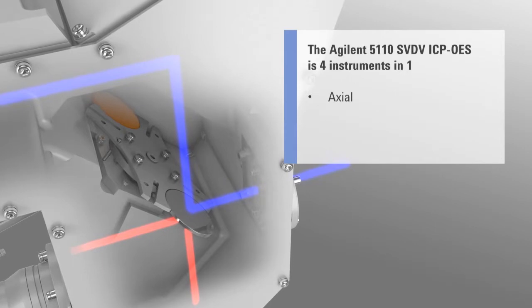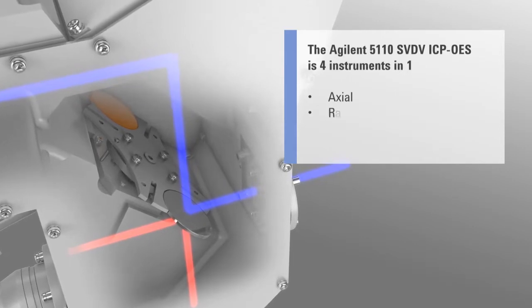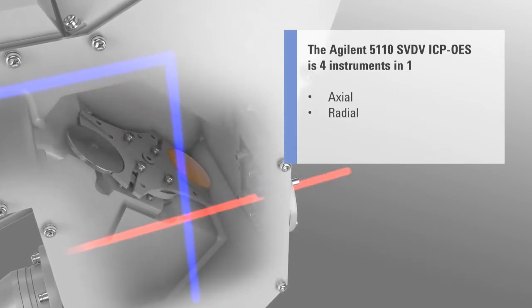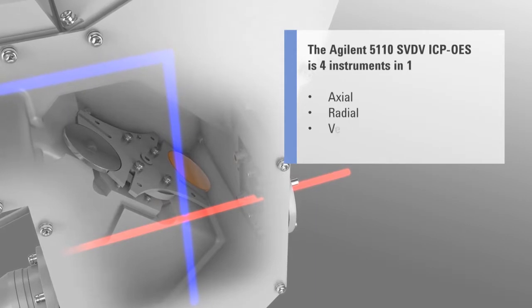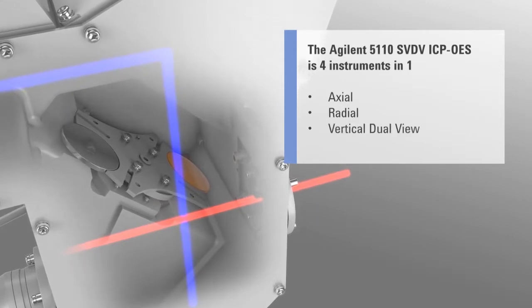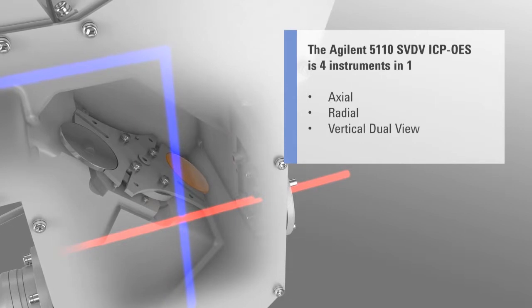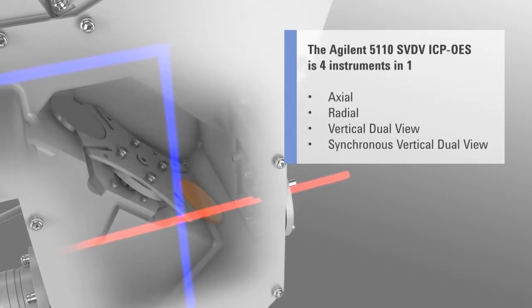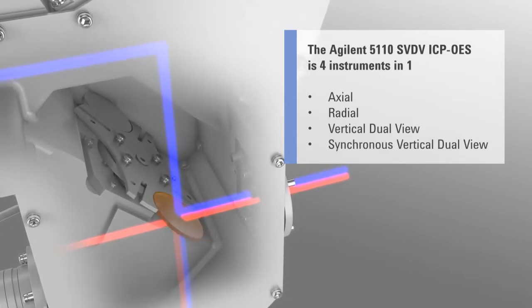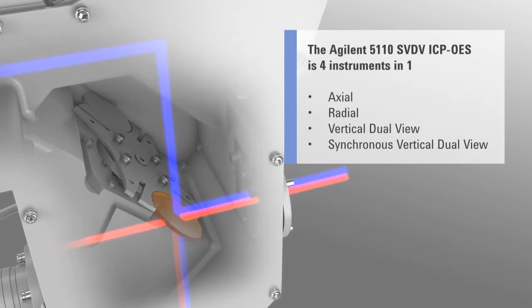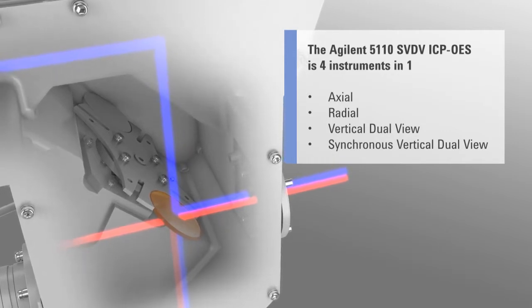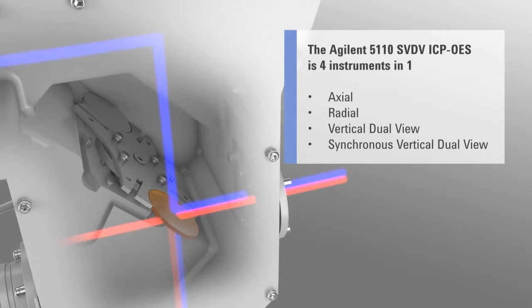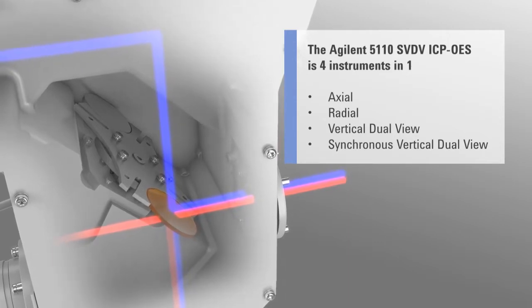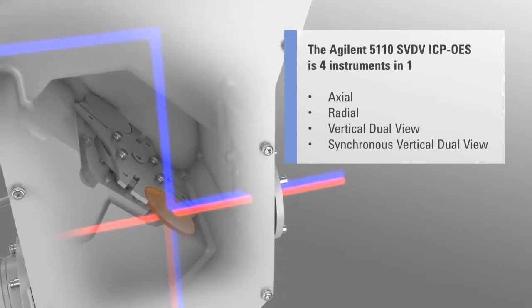This unique technology provides the fastest sample analysis, which creates the lowest gas consumption per sample. The biggest benefit for labs around low gas consumption per sample is that this translates to the lowest cost per analysis and higher profits. The 5110 ICP OES also sets new benchmarks for low power consumption and low exhaust extraction requirements, all of which contribute to the lowest cost per analysis.